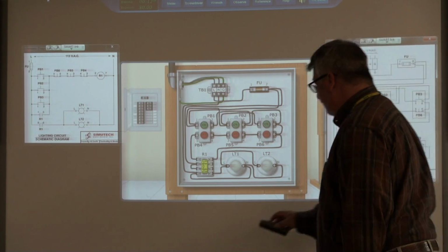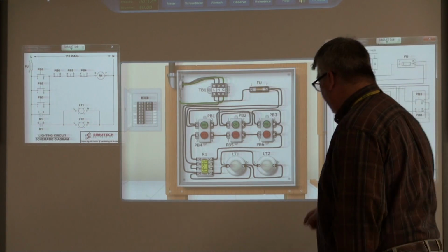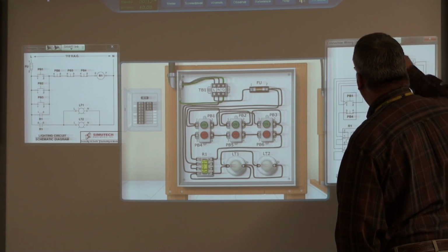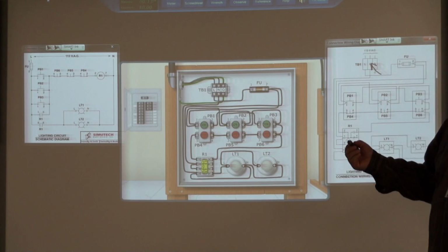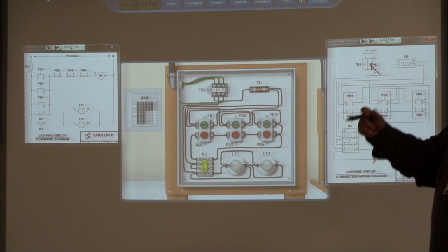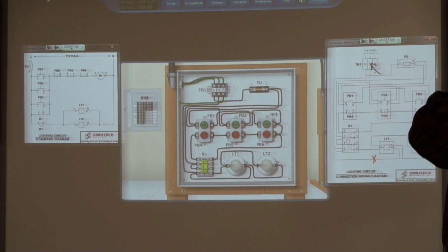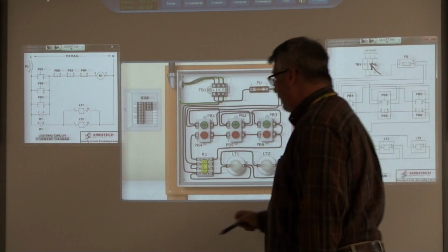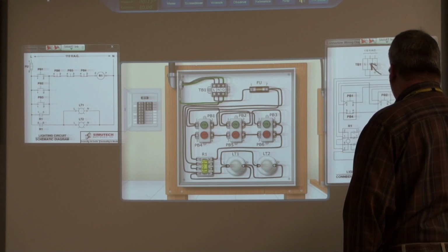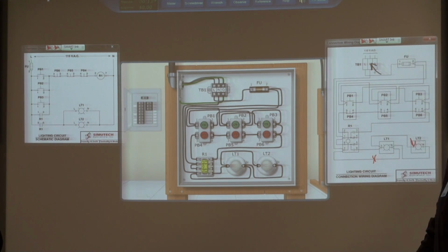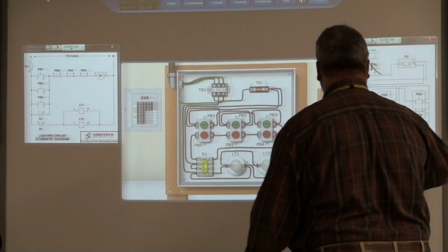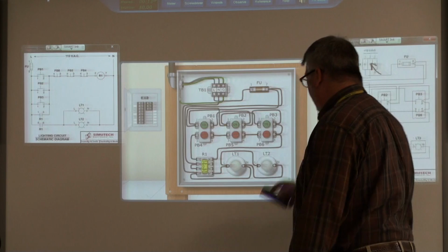Now let's talk about where I'm going to put a probe on ground. I'm going to put a meter probe right here on neutral or ground. Remember, neutral and ground are the same. When you're measuring voltage, it doesn't matter if I put my probe on N or on G, both of those are bonded together in a separate cabinet. So the black probe is right there. What am I going to measure if the red probe is right there? Zero. Very good, because my neutral's open, so I've got no path back to the neutral line.